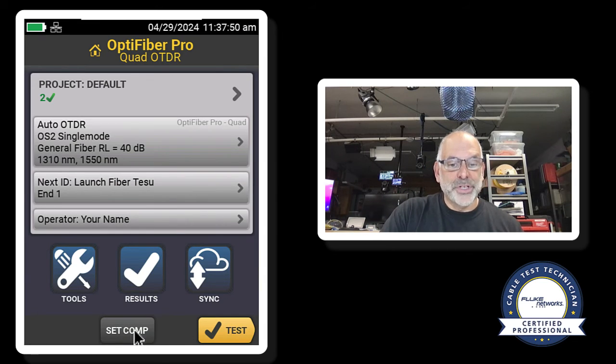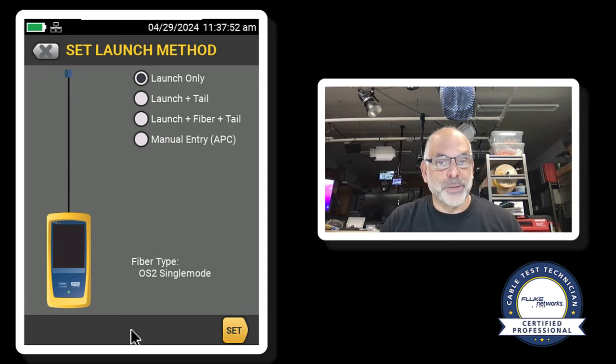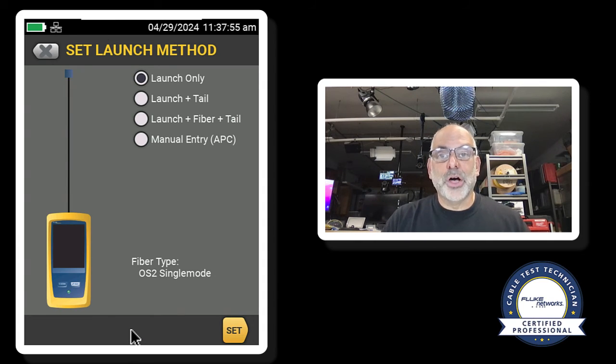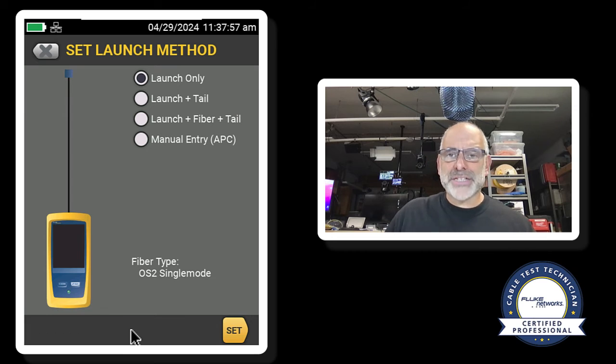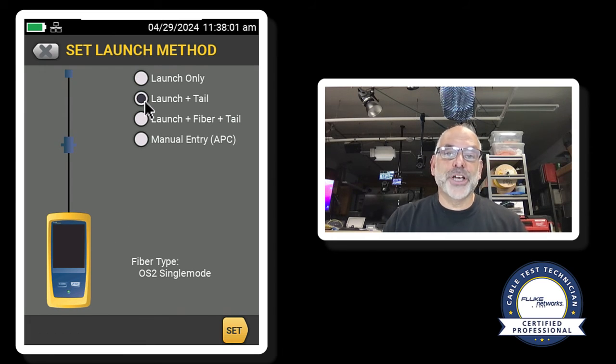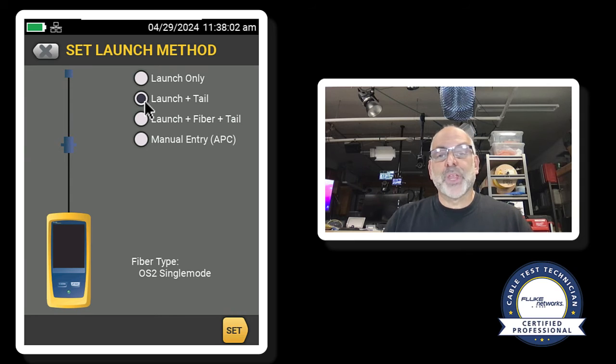So now I'll come back to the home screen again. And I'm going to tap on set compensation. Now in this case, I'm using a launch and a tail, which is the best combination. This allows me to do bi-directional averaging of my link.